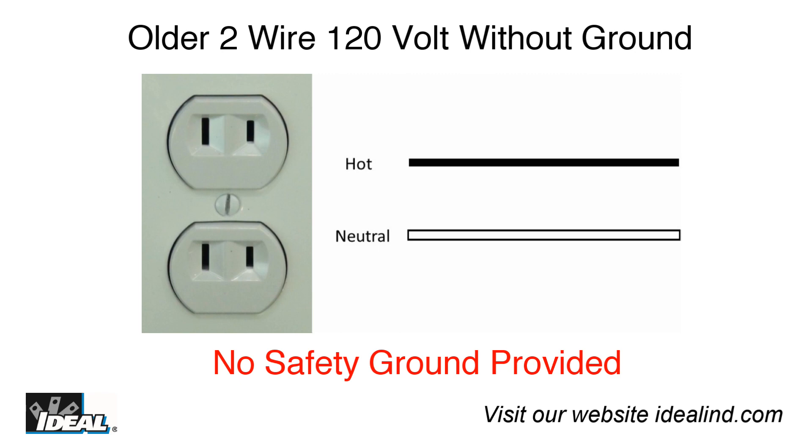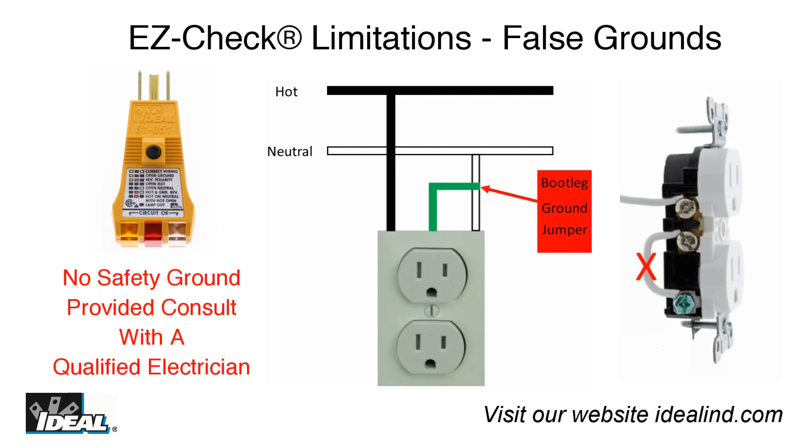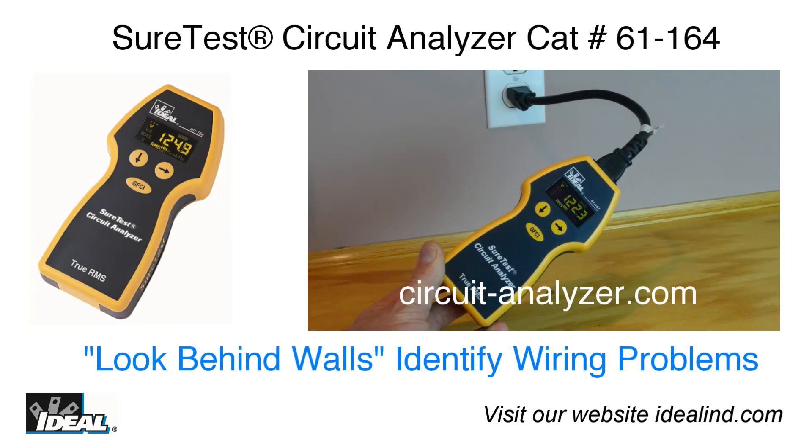Older homes and businesses built prior to this requirement may only have two wire receptacles without a separate ground wire. Simple testers like the EZ-Check receptacle tester are not capable of indicating bootleg or false grounds potentially used to convert two wire receptacles to three wire receptacles. To test for these ground conditions, or to test the quality of the electrical connection under load, other testing will be needed.